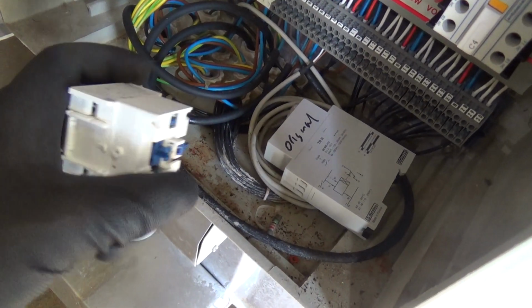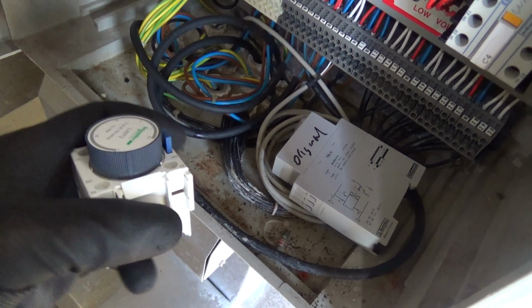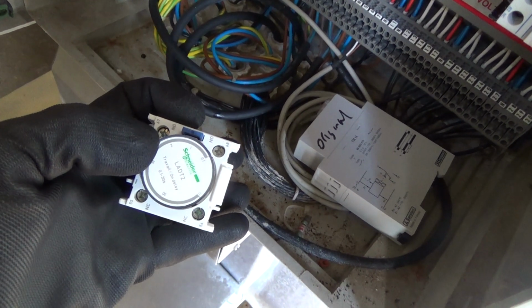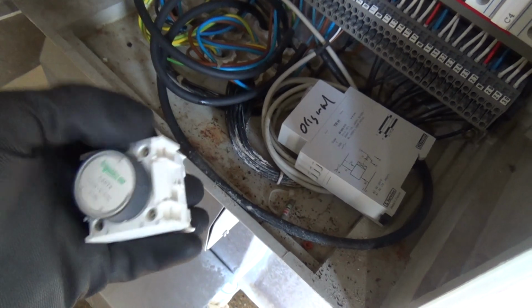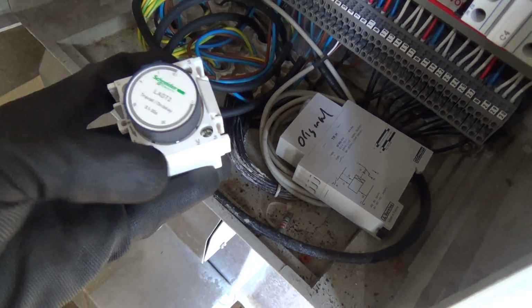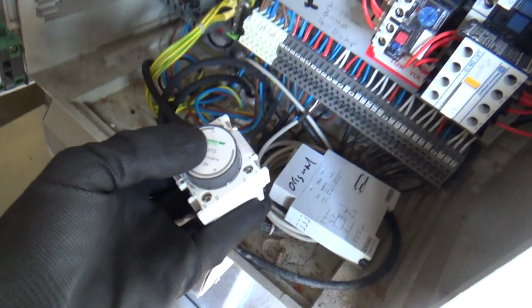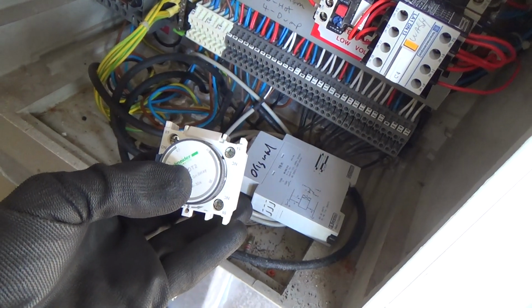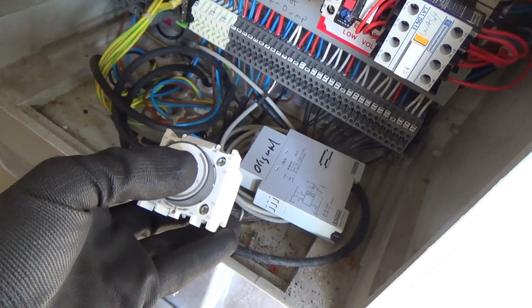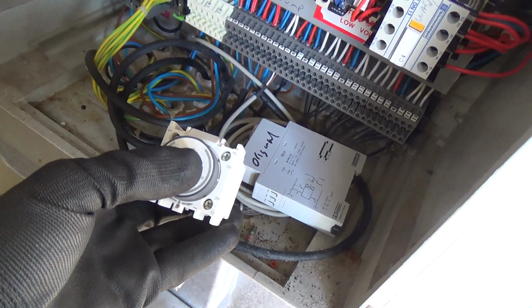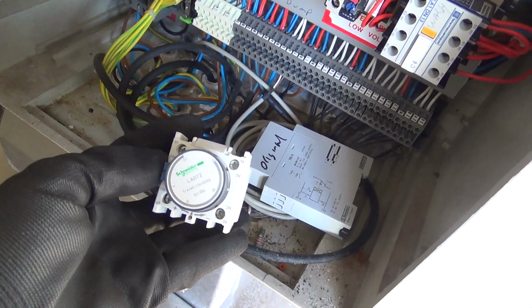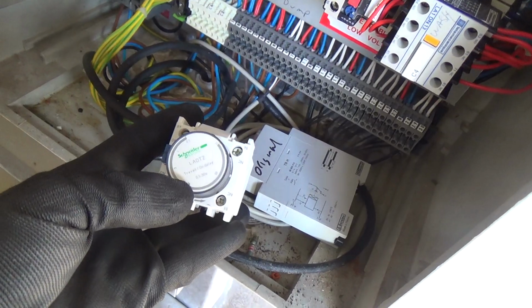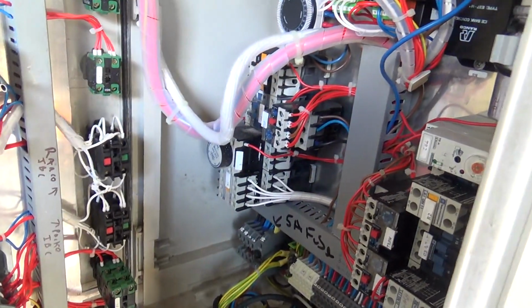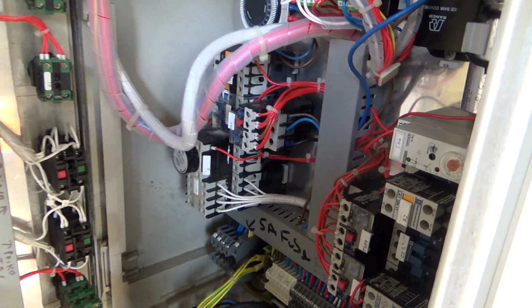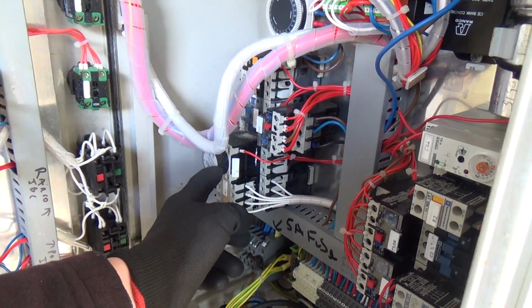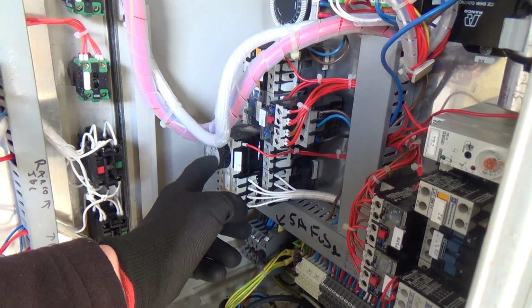When the contactor pulls in, it pulls that in, and then there's a time delay depending on how you set that dial as to when the contacts make across. There's a normally open and normally closed set of contacts, so I quite often see them on star delta time contactors to do the 3-second delay or whatever it's set to. But this one should be set at 10 seconds, and I've timed that at 1 minute 30 something, so it's quite possible it could have been that, and it may have just never switched on.